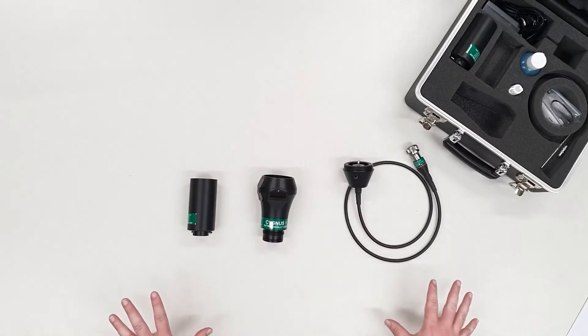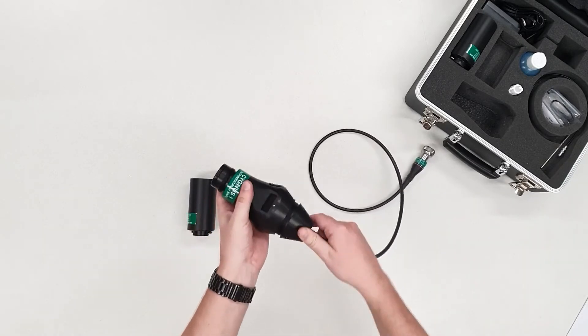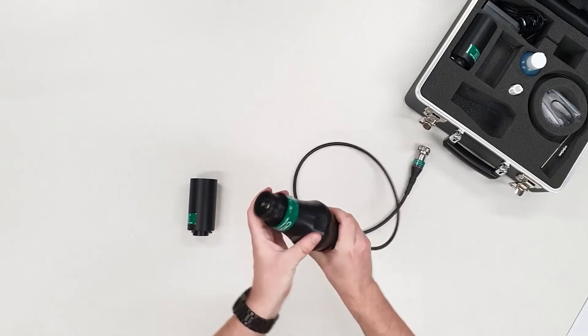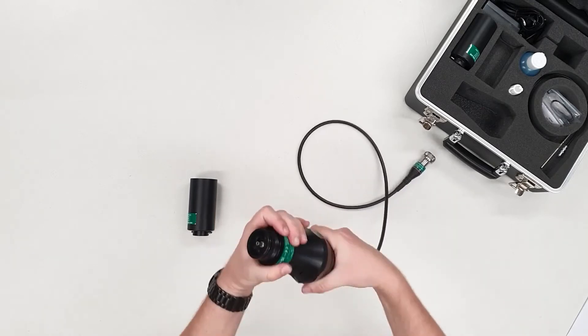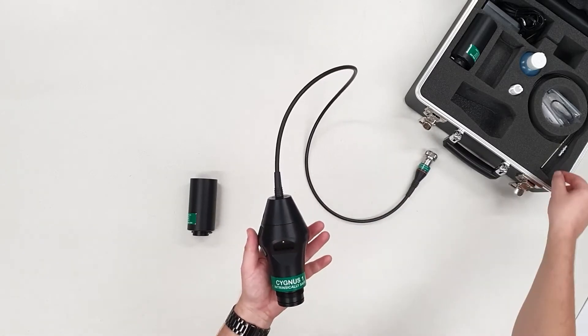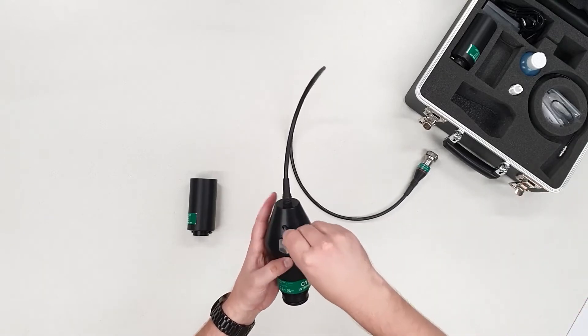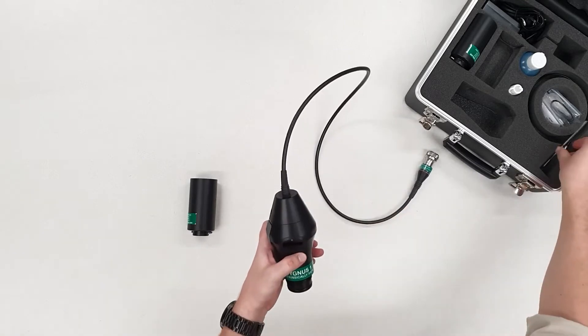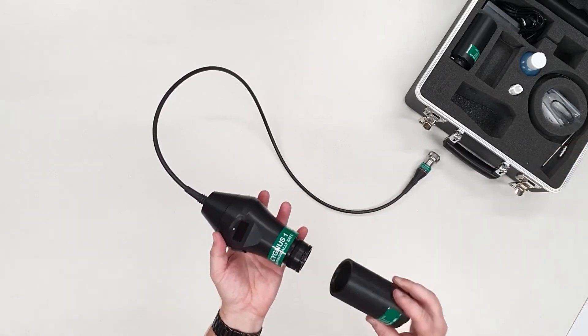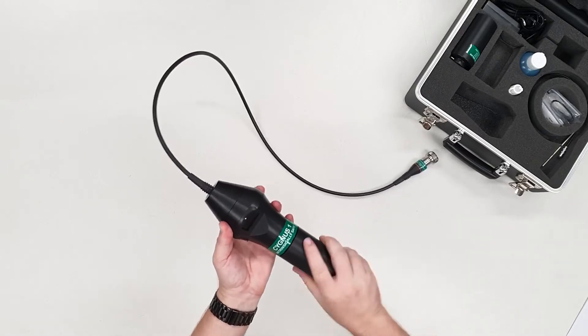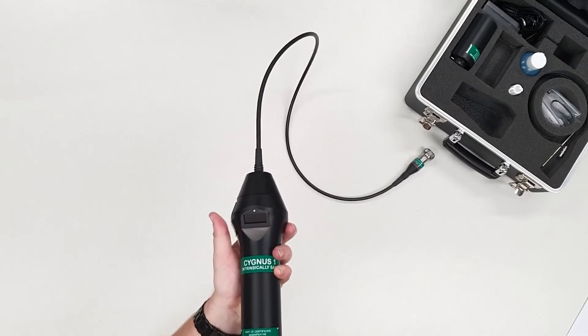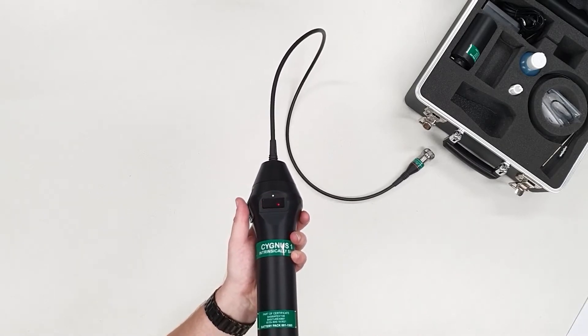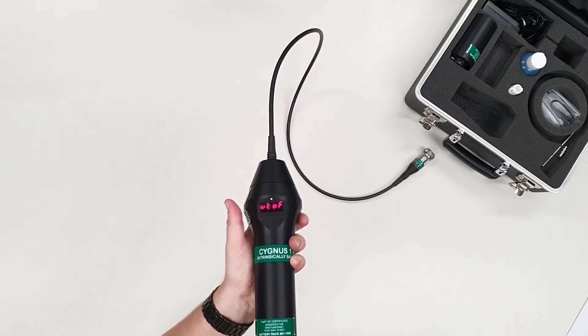Here we have the three main parts. To put it together, first connect the cone of the probe to the body. It only needs to be hand tightened, but if you're having trouble getting it off, the tommy bar can be inserted through the hole here. Once you've got the probe on, the battery connects to the bottom. To turn it on, just press the button on the side. That's ready for operation.